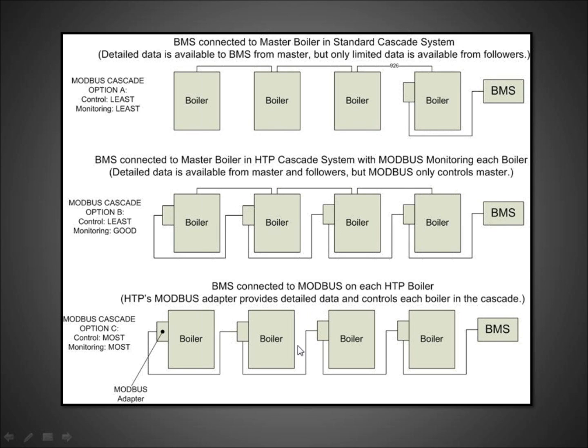And then the final one, which is ModBus Cascade, option C, control is the most and monitoring is the most. So what you're doing here is the HTP ModBus adapter provides detailed data and controls each boiler in the cascade. So in other words, the ModBus in this example is controlled from the building management system, and then the adapters can read information based on what the customer's needs are and what they want to control. Right, and in that third scenario, the BMS actually controls the cascading of the individual boilers. Okay.